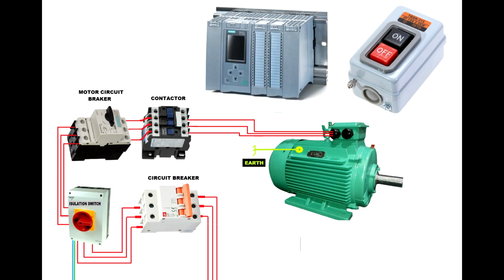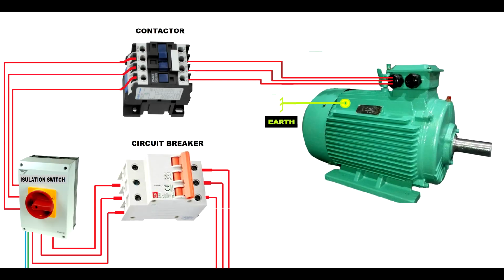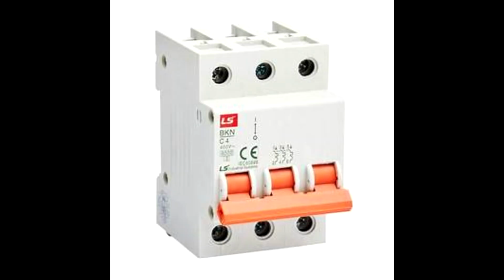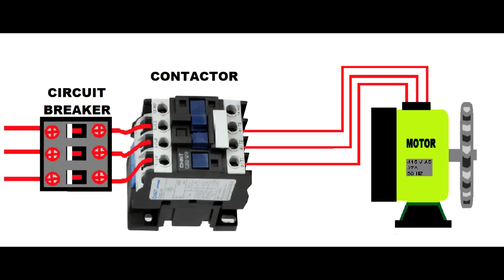It could be either switches or a programmable logic controller. Let's talk about poor design circuits without motor overload protection. You'll see in this picture we have on our circuit a circuit breaker, an isolating switch, a contactor, and the motor. There's no motor overload protection integrated into this system, and the circuit breaker protects the circuits, the wires, not the motor. Let's see why this specific arrangement is not healthy.